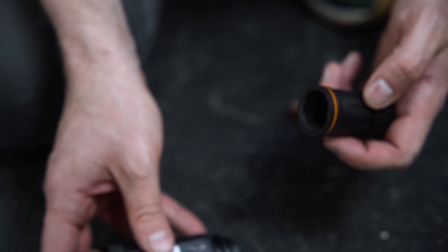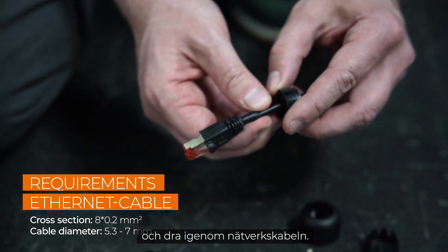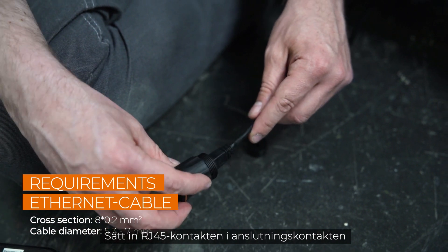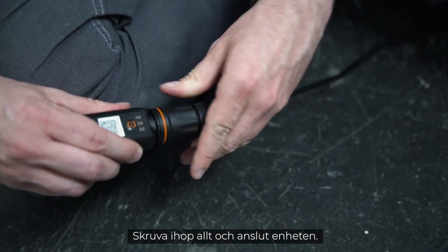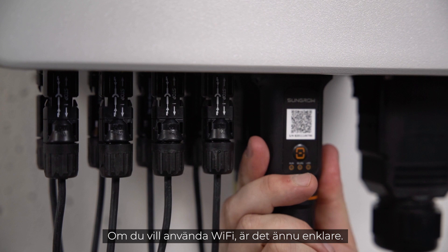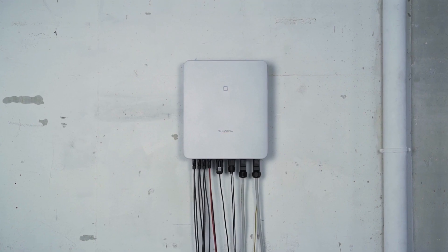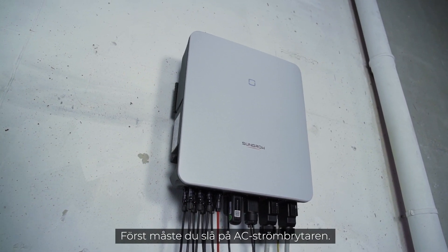For commissioning you have to connect the new WiNet module, which combines Ethernet and Wi-Fi in one port and is part of the delivery scope. If you want to use Ethernet, unscrew the swivel nut from the WiNet-S, thread the network cable through it, insert the RJ45 plug into the plug connector until you hear a click, then screw everything together and plug the device in. If you want to use Wi-Fi, it's even easier — simply connect the module to the inverter.